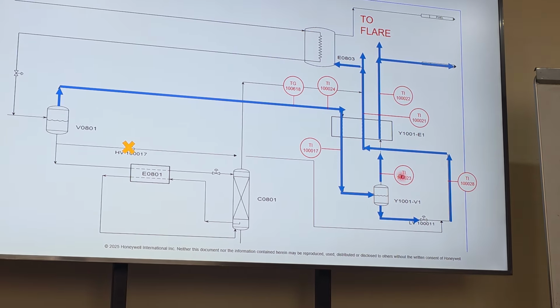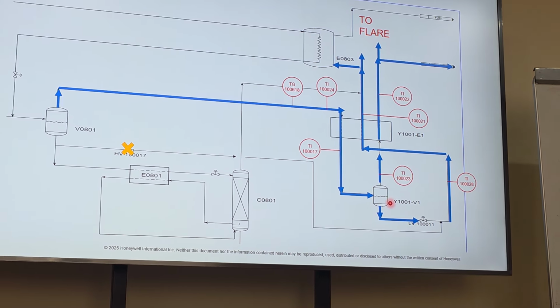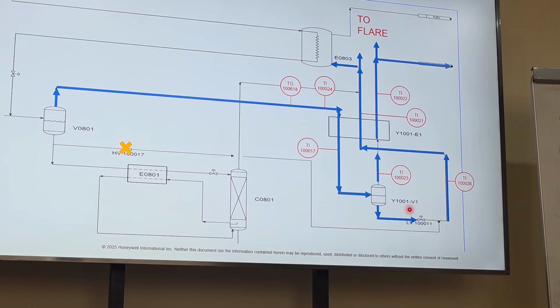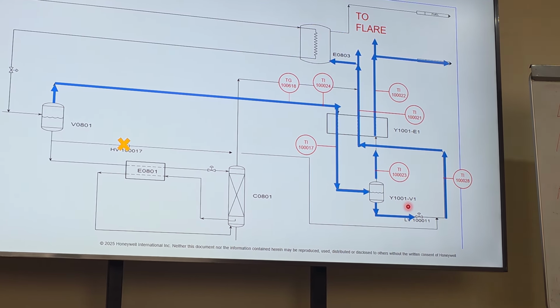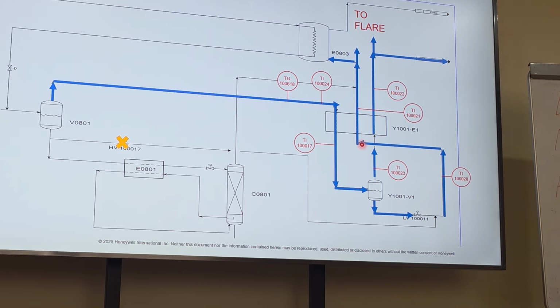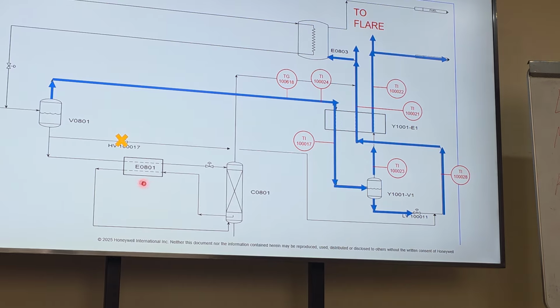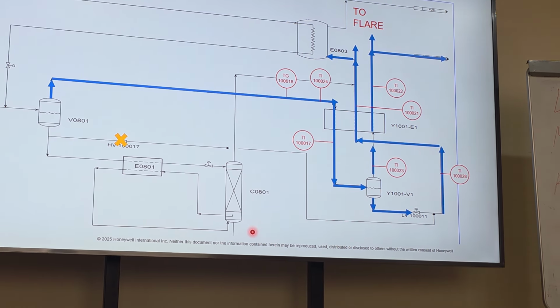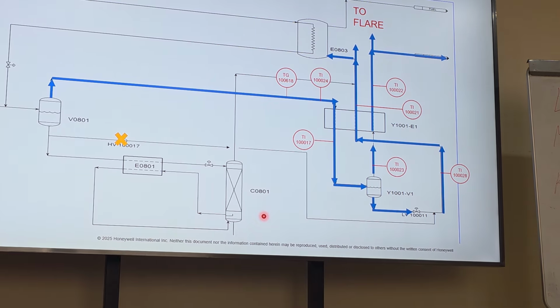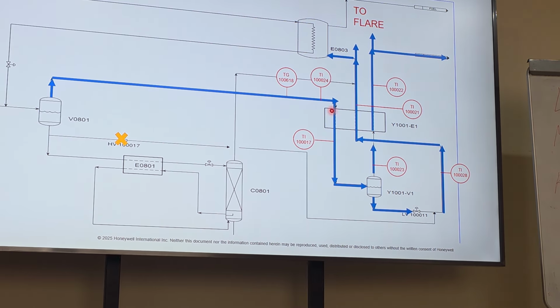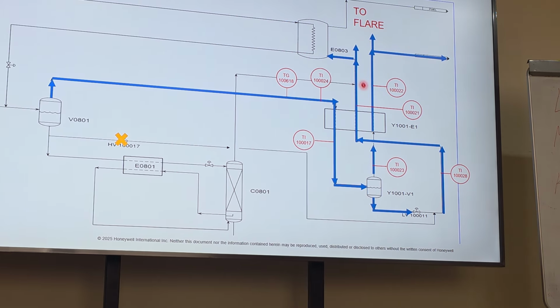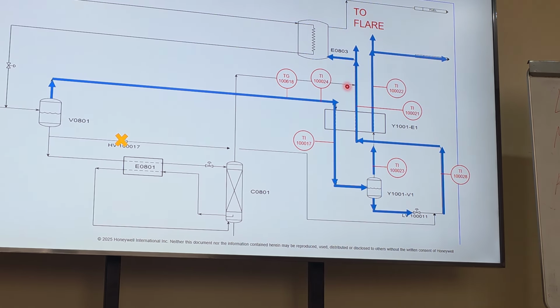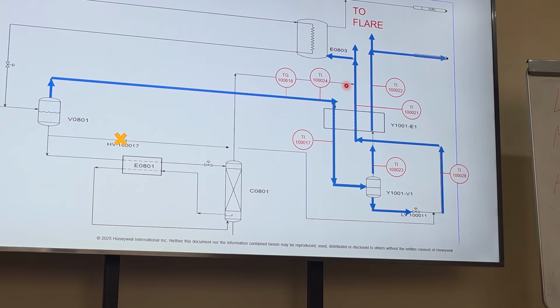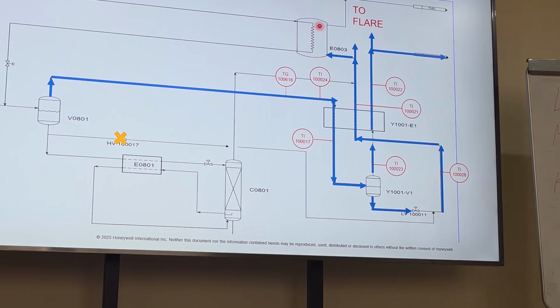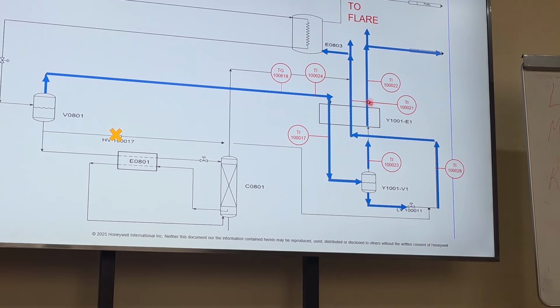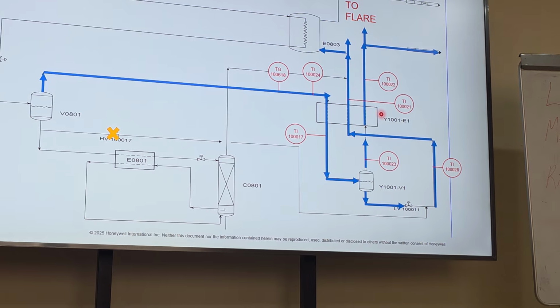Now, you want to be careful that you don't get too cold in unit 10, because you're stepping it down in this flash drum again and that will create some refrigeration. Something to be aware of: you want to pay attention that unit 10 doesn't start to outpace unit 8. So we just keep the pressure higher so that it won't. And the nice thing is, as you're cooling down unit 8, this is getting cold. So when you reblend this gas off the top of your column with the helium, once again, pay attention: no more than 28 degrees C difference, and make sure you're not going to make the E0803 too cold.